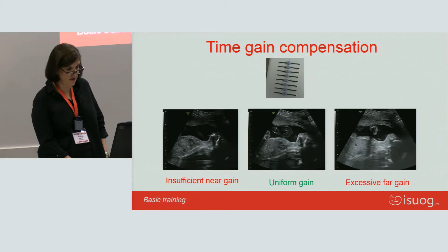I've just realized that the pointer is not on. So the near, the middle, and the far gain. The picture in the middle, you can see there's uniform gain throughout that whole image. The picture on the left, you can see closest to the footprint is quite dark. And that is because the time gain compensation in the near field is set too far to the left. And that's why it's black. And the one on the right, there's excessive gain in the far field. So those little paddles have been moved all the way to the right. I'm sorry, to the left in the top and to the right in the third image on your right. So those little paddles in the middle have to all be sort of down the middle to give you uniform gain.